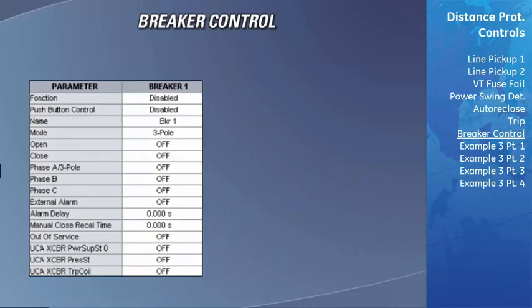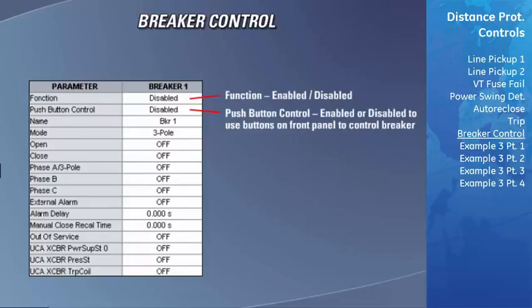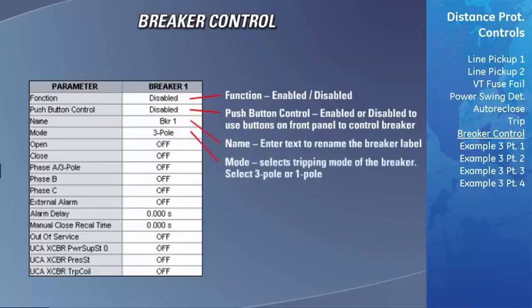correctly. As for all elements in the D60, if you wish to use this feature, you must enable it in the function field. If you wish to use the push buttons on the front panel of the UR to control the breaker, the push button control field must be enabled. If you wish to rename the breaker, you can do so by typing text into the name field. The mode setting determines if the breaker will always be tripping all three phases for all faults, or will be tripping only one phase for a single phase fault. In this field, select 3-pole or 1-pole.